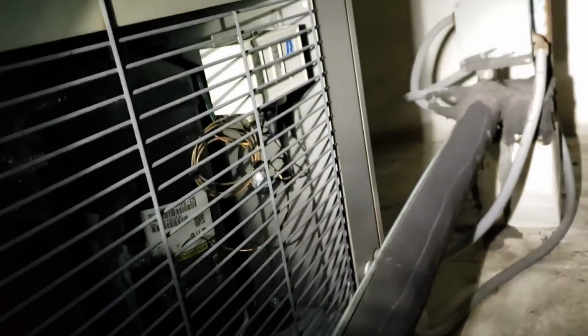We got a pressure switch in place, but it's not ideal, I guess. It'll work. I'll note it, and I can't imagine they're going to give me approval to shut the whole system down, pump everything down, pump it out of the system and valve it off right here, and then put it on properly. But we'll see. Anyway. Nothing too crazy up here.